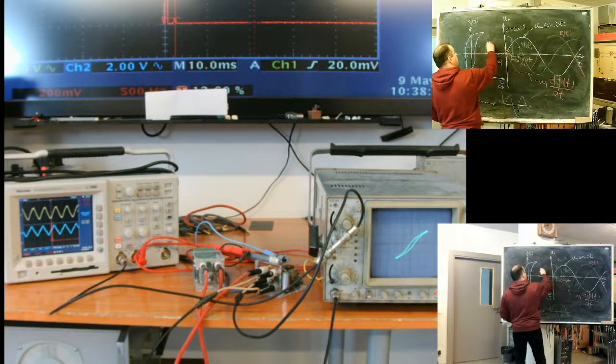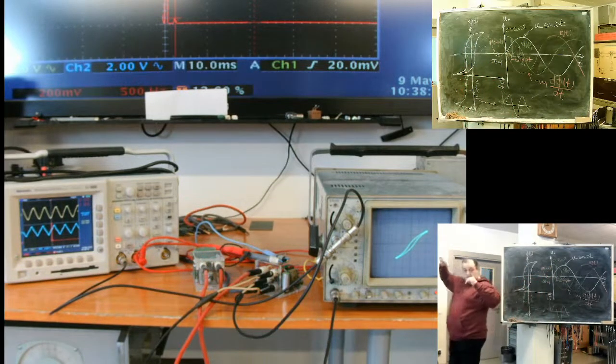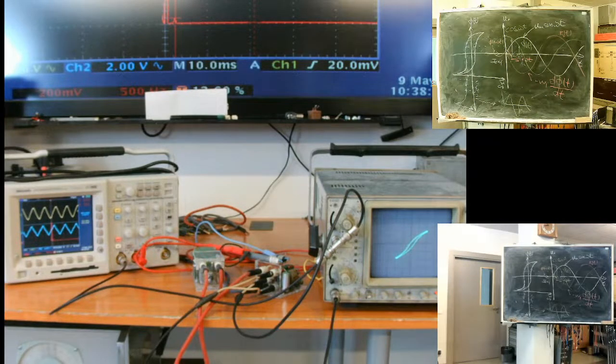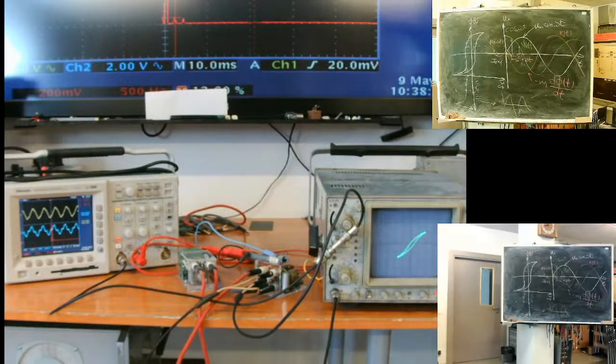It's a flux at three omega. And flux will have distortions. Now flux is not cosine. And these distortions appear in secondary voltage. Very loudly. You can see it. It's clearly third harmonics.